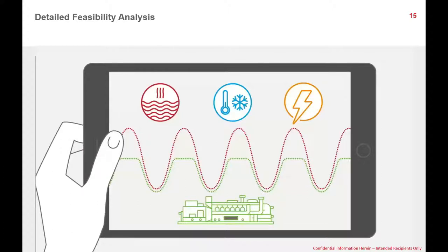A gas engine operates most optimally when it's running at as high a load as possible for as long as possible. But it does have an operating window down to 40 or 50% of its rated output, depending on the unit. So understanding partial load conditions, such as during evenings and weekends, is fundamentally important.